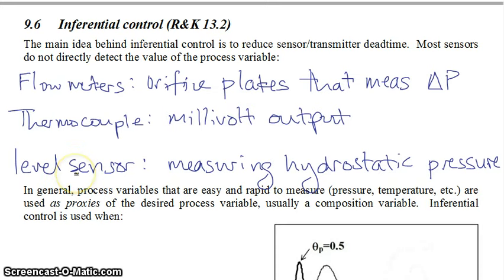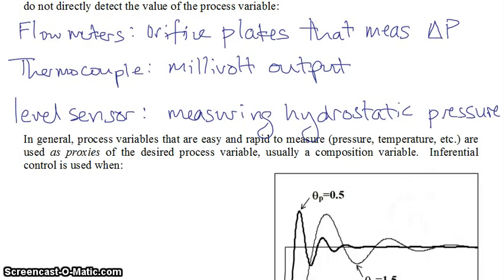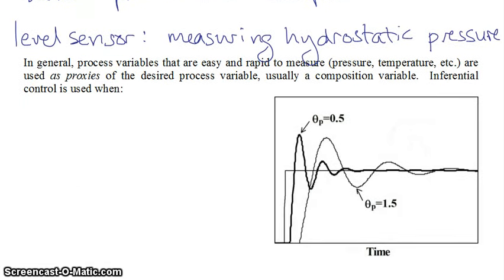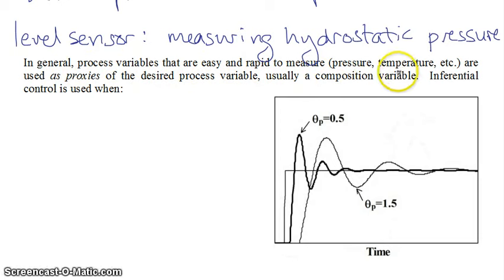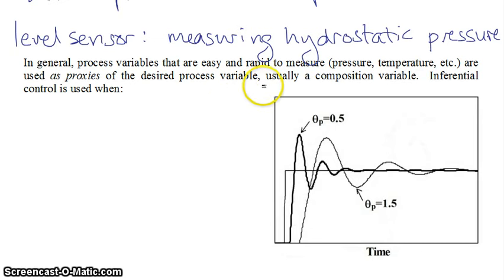But there are assumptions that go into it. Specifically for a level sensor, if it's measuring hydrostatic pressure and converting that into a level, you better be sure that you know what the density of your fluid is. And the same thing is true in inferential control — you need to have a model, but it needs to be a good model. In general, you have process variables that are easy and rapid to measure, things like pressure and temperature, and these can be used as proxies for your desired process variable.